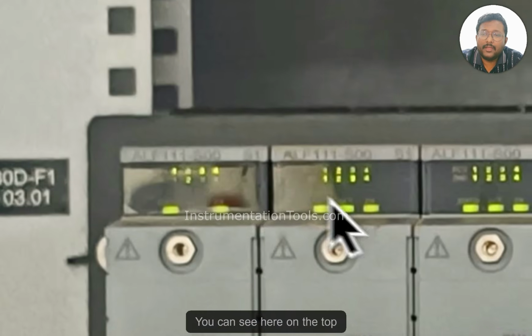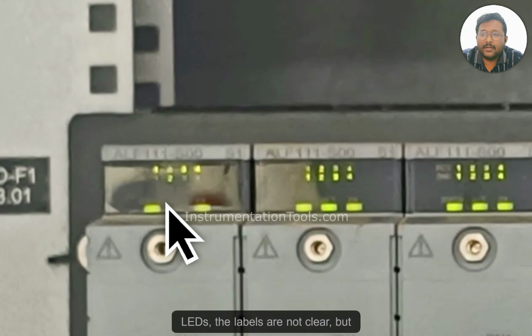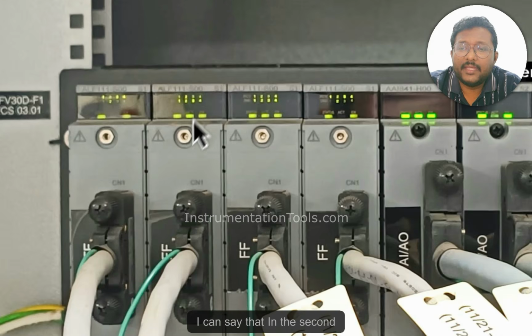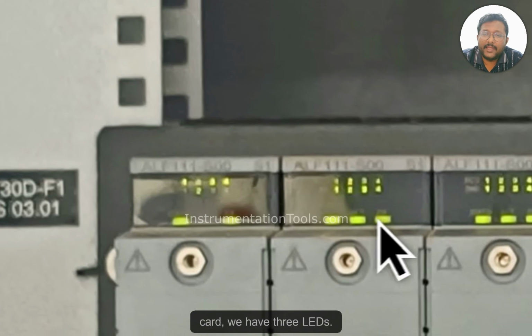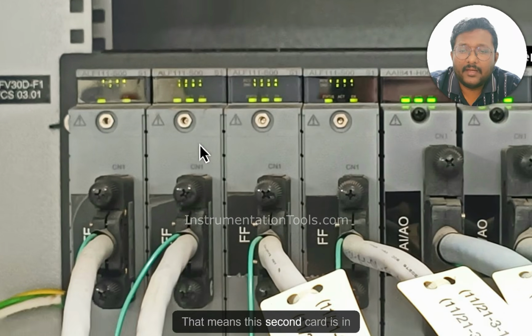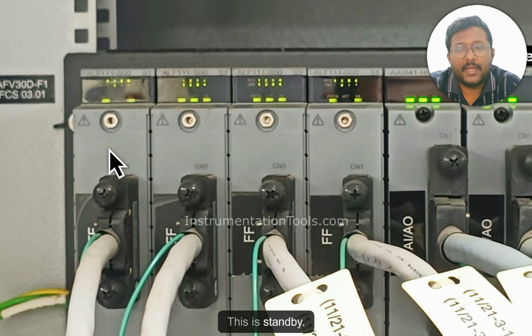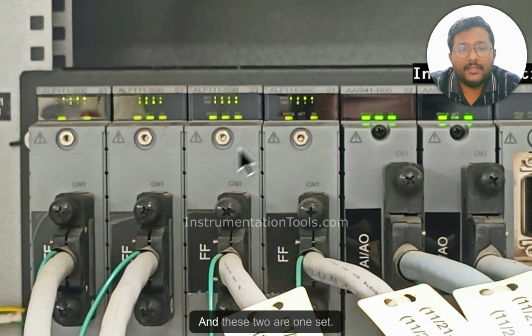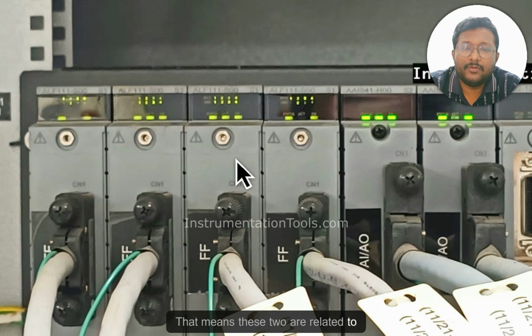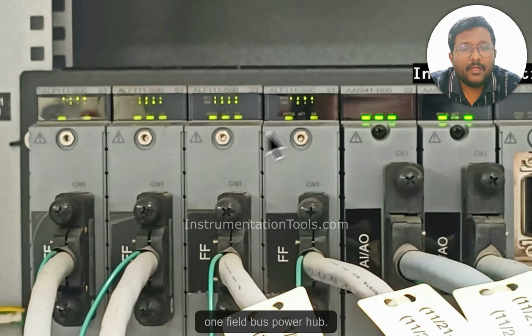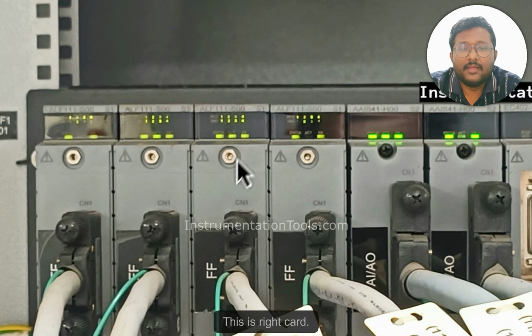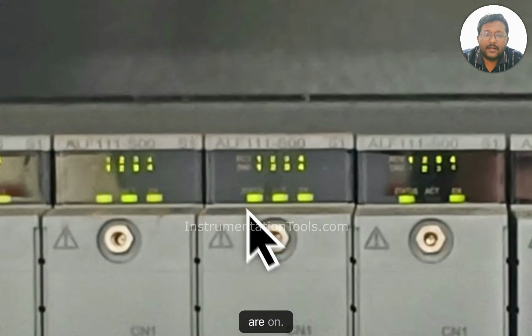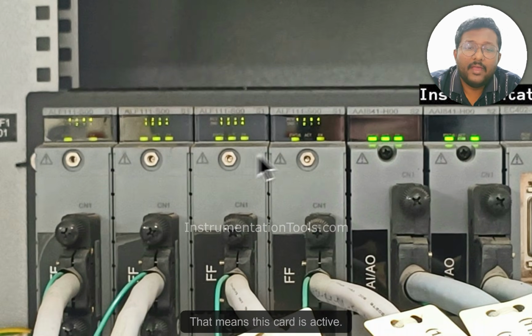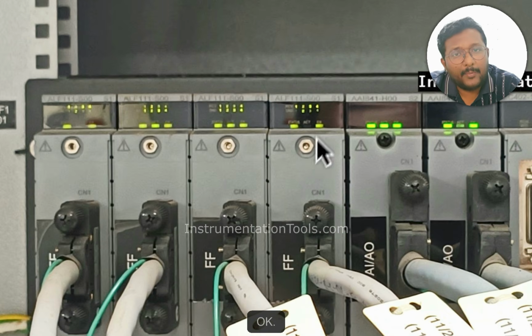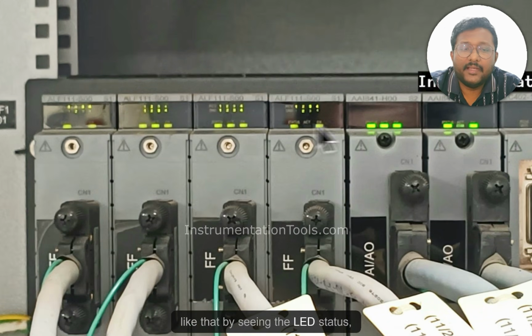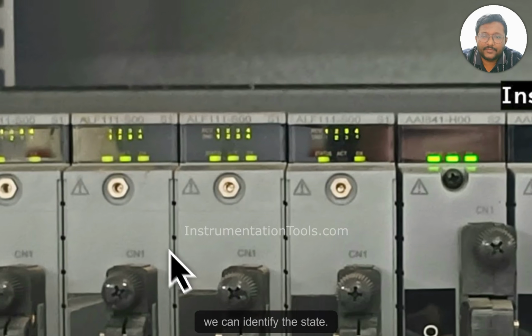You can see here on the top LEDs, the labels are not clear, but I can say that in the second card we have three lights, three LEDs. That means this second card is in control. This is standby. Like that, and these two are one set. That means these two are related to one fieldbus power hub. This is the left card, this is the right card. In the left card, all three LEDs are on. That means this card is active, and the next card is in standby mode. Like that, by seeing the LED status, we can identify the state.